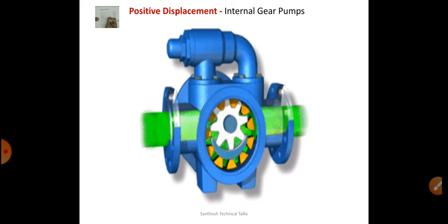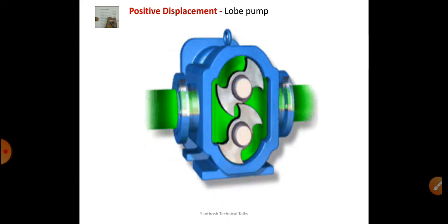The gear pump is directly coupled with the crankshaft of the engine, so we cannot stop the gear pump. If we want to stop the gear pump, we have to shut down the engine, so stoppage is not at all possible, whereas the relief of the pressure is possible, and it acts like a safety valve.